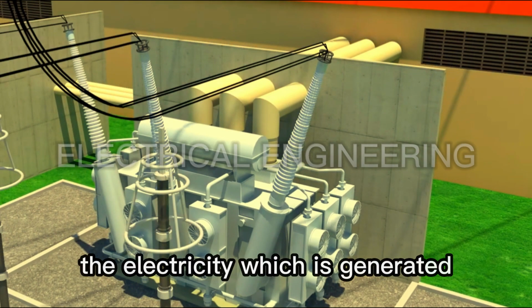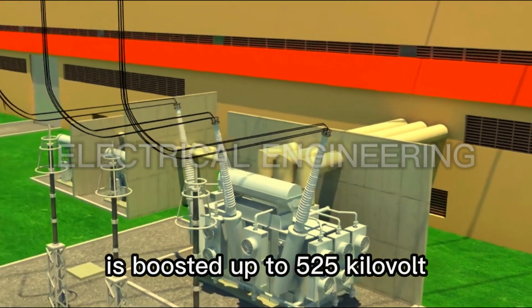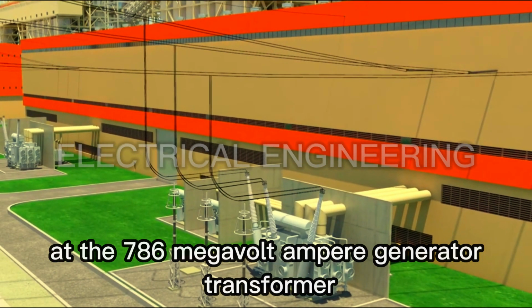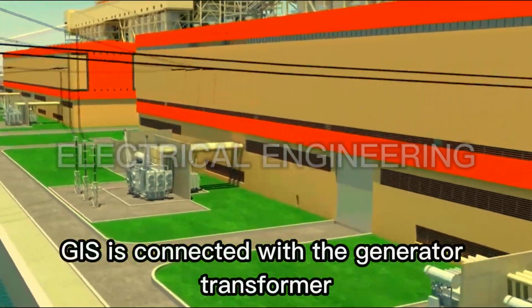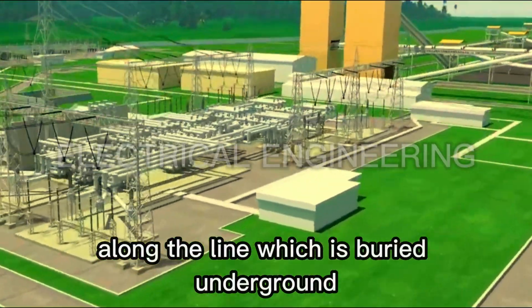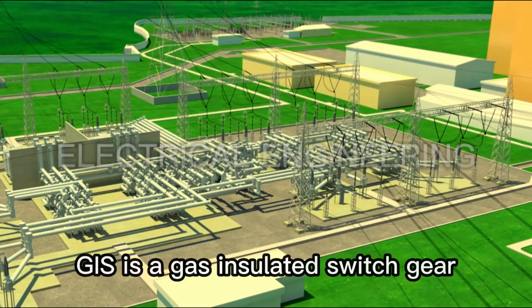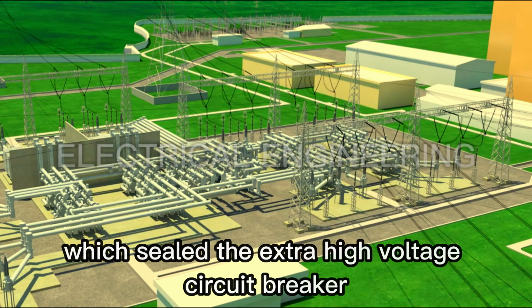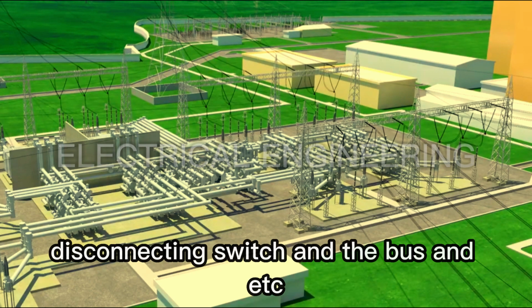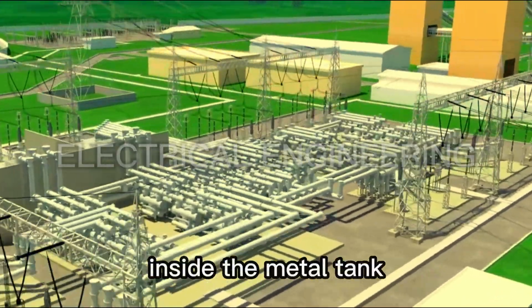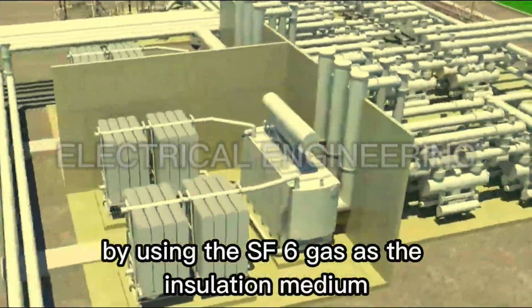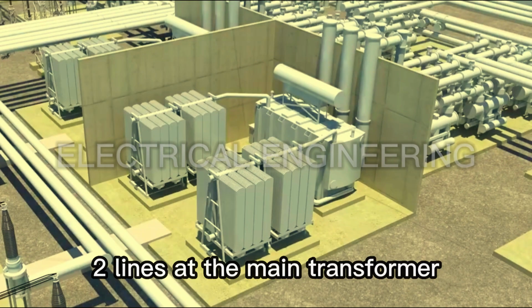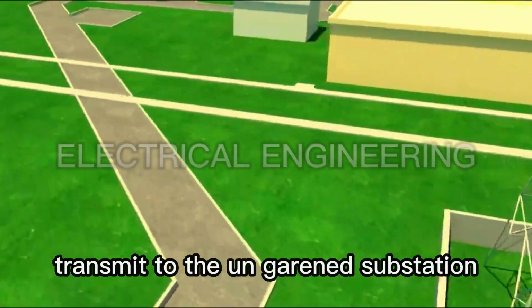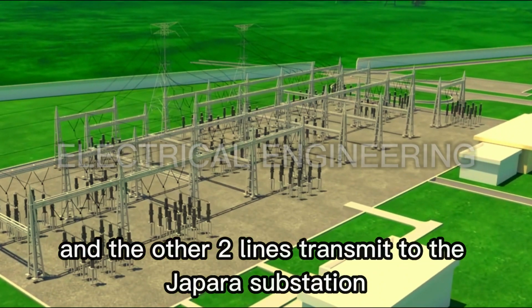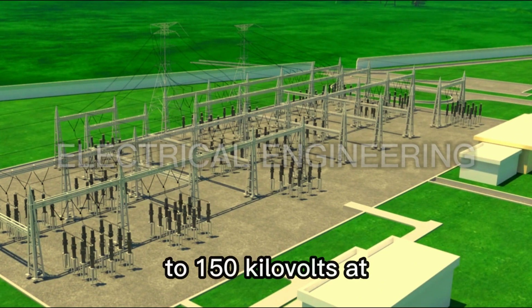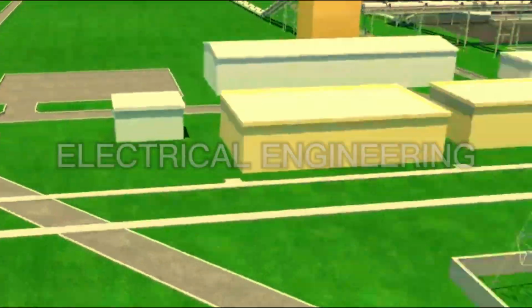The electricity which is generated is boosted up to 525 kV at the 786 megavolt ampere generator transformer. GIS is connected with the generator transformer along the line which is buried underground. This is a gas-insulated switch gear, which sealed the extra high voltage circuit breaker, disconnecting switch and the bus etc. inside the metal tank by using the SF6 gas as the insulation medium. Two lines at the main transformer transmit to the Ungaran substation, and the other two lines transmit to the Japara substation after being transferred to 150 kilovolts at the interbus transformer.